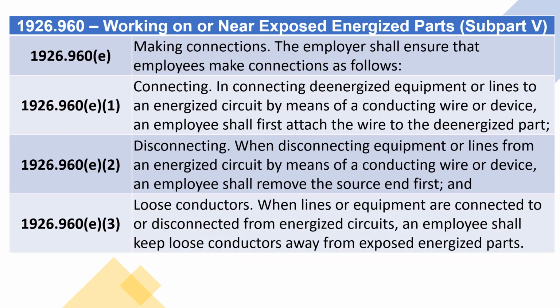1926.960(e) Making connections. The employer shall ensure that employees make connections as follows. 1926.960(e)(1) Connecting. In connecting de-energized equipment or lines to an energized circuit by means of a conducting wire or device, an employee shall first attach the wire to the de-energized part. 1926.960(e)(2) Disconnecting. When disconnecting equipment or lines from an energized circuit by means of a conducting wire or device, an employee shall remove the source end first. 1926.960(e)(3) Loose conductors. When lines or equipment are connected to or disconnected from energized circuits, an employee shall keep loose conductors away from exposed energized parts.